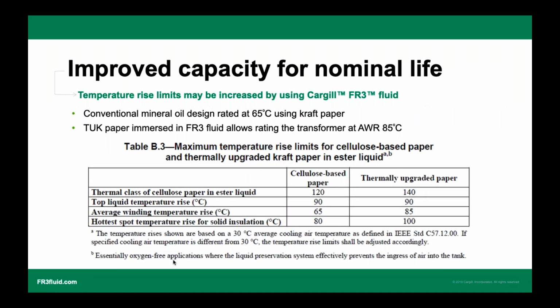So if you have designed your transformer for the conventional temperature rise at 1, then definitely with the revised temperature rise we can go as high as 1.5 times, and that's typically a global trend nowadays. You can save on the losses of the transformer by right sizing, selecting a smaller size transformer where you have a load coming in the future. Let's move on to the next. Again, an extract from the standard.